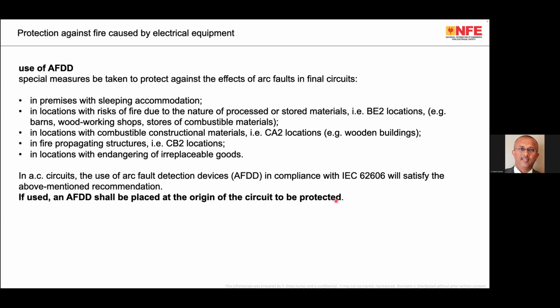What happens is, the AFDD is a very sensitive device which will detect continuous arcing happening in a circuit. If the arcing is more than a certain energy, for example 2.5 amperes, then the device trips. Please note that using electricity safely is one requirement. Similarly, continuity of power supply is also a mandatory requirement. Nuisance tripping should not disrupt the power supply. Each of the protective devices has to be selected and erected in such a way that it operates only when that kind of condition exists.